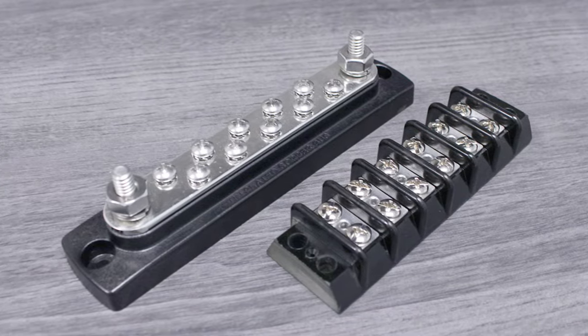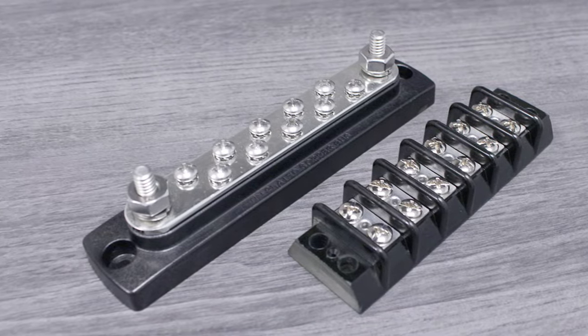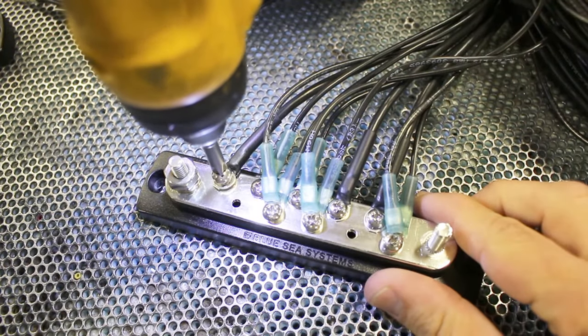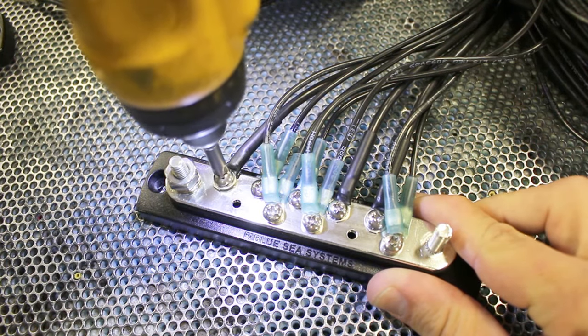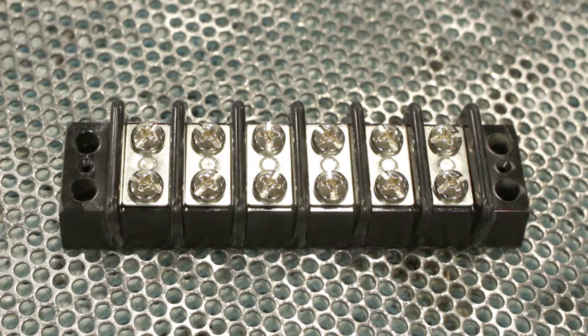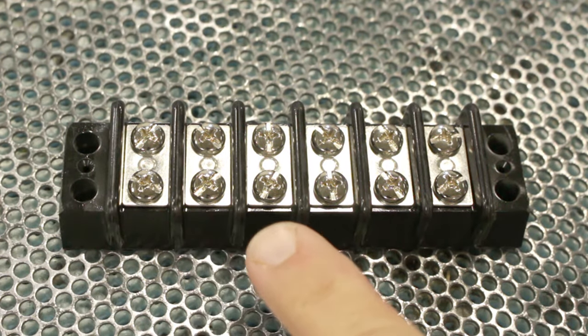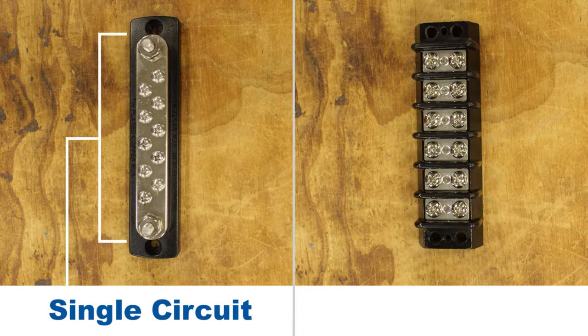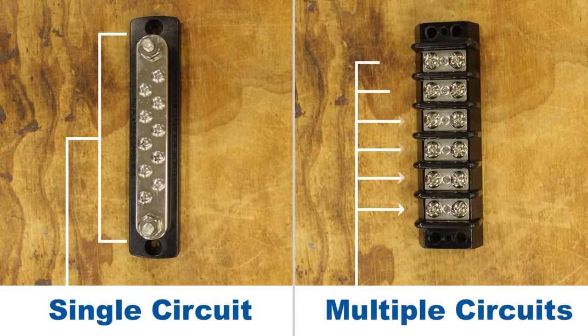Although they have similar visual appearances, bus bars and terminal blocks serve very different purposes. The main difference between a bus bar and a terminal block is that a bus bar gathers multiple wires together for electrical distribution in a single circuit. By contrast, a terminal block has separate circuits where each incoming wire is paired with an outgoing wire. A simple way to think about it is that a bus bar is a single circuit and a terminal block is multiple individual circuits.